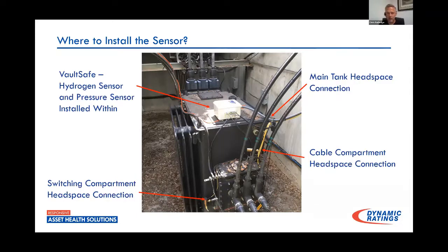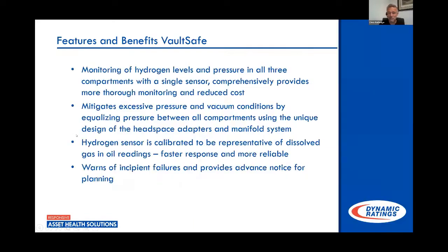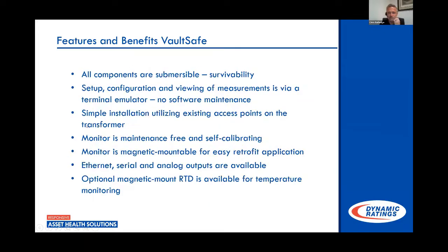I've done several of these by myself, and there's actually a video on our website if you want to go to it. It takes me about 45 minutes to put one in. So I'm going to just kind of run to the end of this. Also, we can do a mag mount RTD. That's optional. If you would like to bring temperature in, we have some inputs available to do that as well. So you could look at top oil temperature to see how the flux of hydrogen between oil is being affected by temperature. If you wanted to bring that in, that's also a good thing to have to look at.